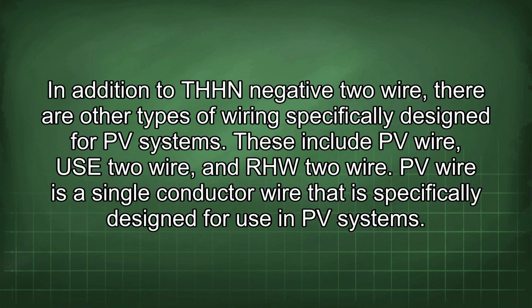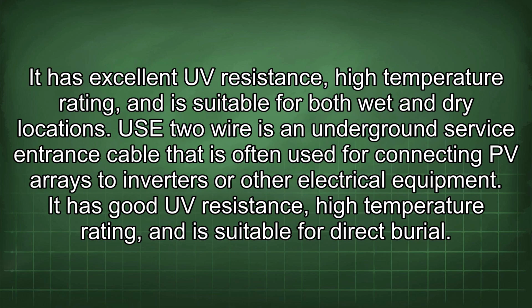In addition to THHN-2 wire, there are other types of wiring specifically designed for PV systems. These include PV wire, USE-2 wire, and RHW-2 wire. PV wire is a single conductor wire that is specifically designed for use in PV systems. It has excellent UV resistance, high temperature rating, and is suitable for both wet and dry locations.